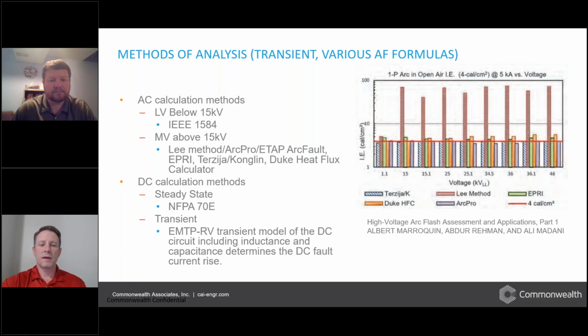For DC, the main formula to calculate arc flash is NFPA 70E. So we'll take the short circuit current from ETAP or some other program like it, and then we'll either run arc flash inside that or we'll calculate it ourselves in a spreadsheet.